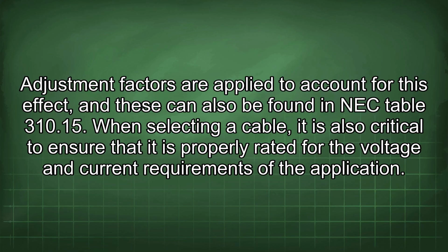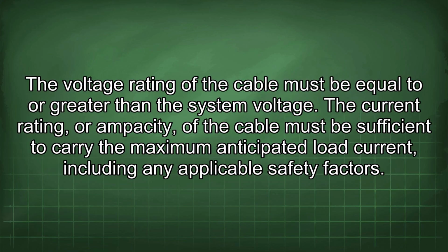When selecting a cable, it is also critical to ensure that it is properly rated for the voltage and current requirements of the application. The voltage rating of the cable must be equal to or greater than the system voltage. The current rating, or ampacity, of the cable must be sufficient to carry the maximum anticipated load current, including any applicable safety factors.